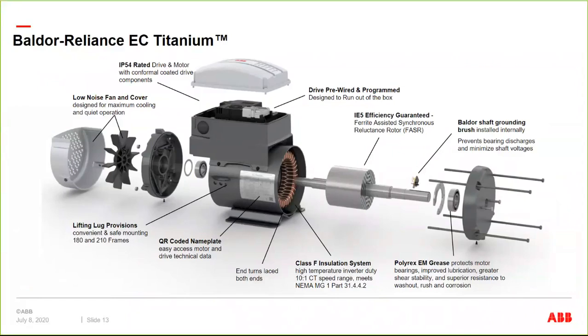However, because of the low losses and high power factor and extremely cool running product, it's only a Class B rise. So I've had the question, is it a Class H insulation? Well, no, but you don't need it. What you really want is to keep the temperature rise of the motor down. So you don't need Class H if you have a Class B rise motor. And so that's a very cool running motor with a Class B rise.